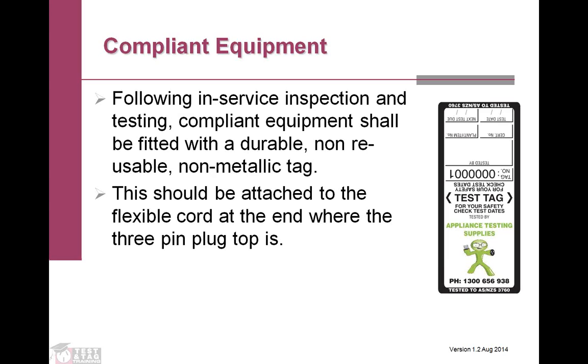The information that needs to be on there is the person or company that conducted the test. If done in-house, it can be as simple as a tester's ID, which can be an initial, plus the test date and the next test due. There are other areas on most tags for things like certification numbers and plant numbers, but they're only optional—they don't need to be there. The tag just has to have the details on who tested it, the test date, and when the next test is due, attached to the plug end of the lead.